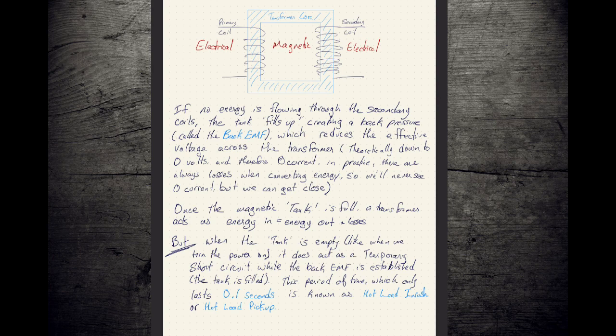And the first of those is if you get a fault on the secondary side of the transformer. If you get a fault here, all of a sudden, the energy flows out as fast as it flows in. This is like having a breach in your tank. And now all of a sudden there's no back EMF. This is going to suck energy into it and across that core as fast as it's able to try and feed that fault over here. And you'll see that as a fault-like energy flow, current flow on the primary side.